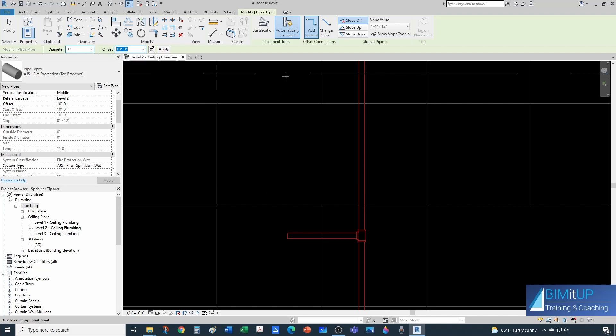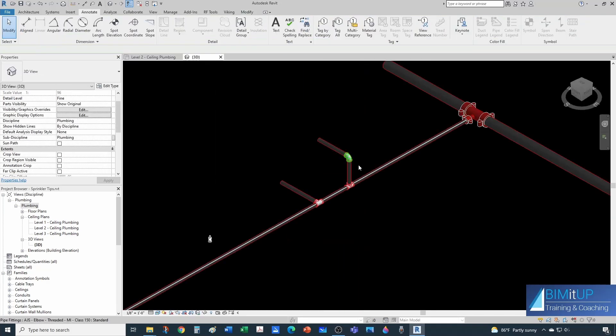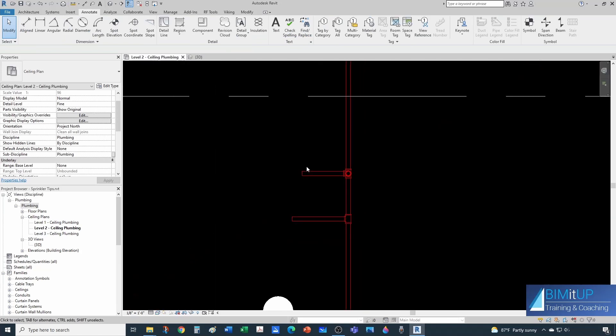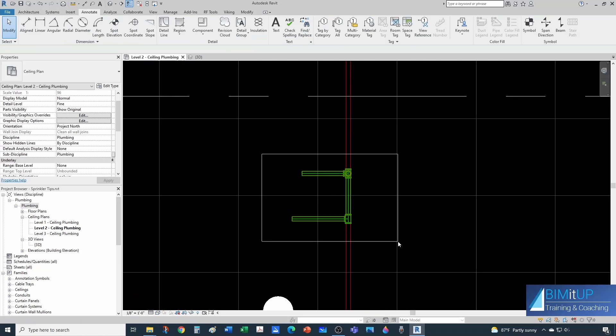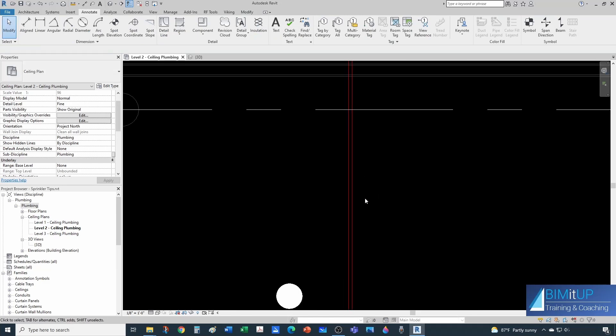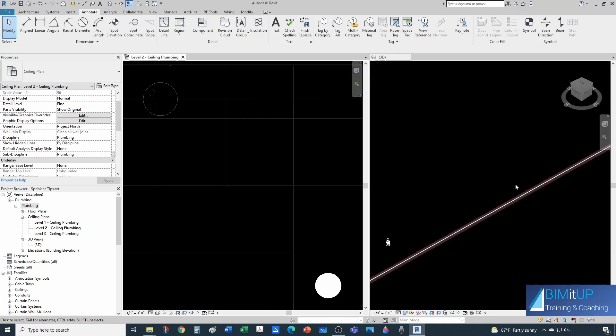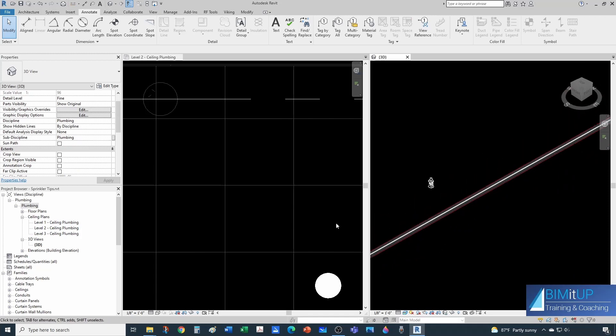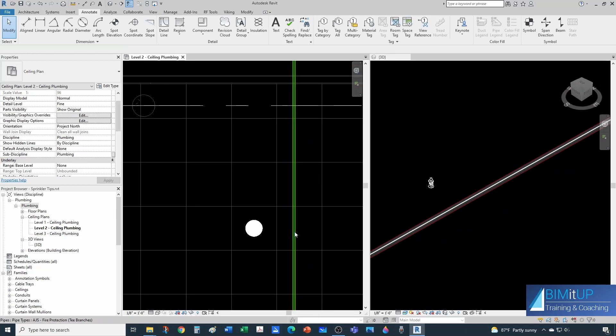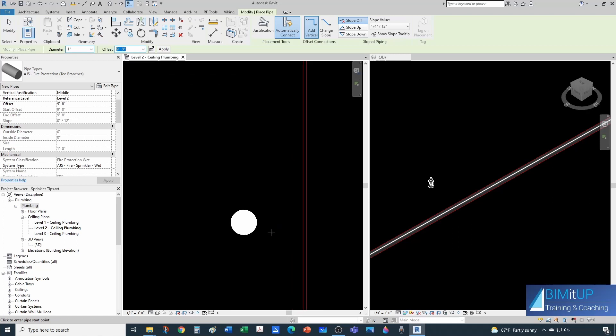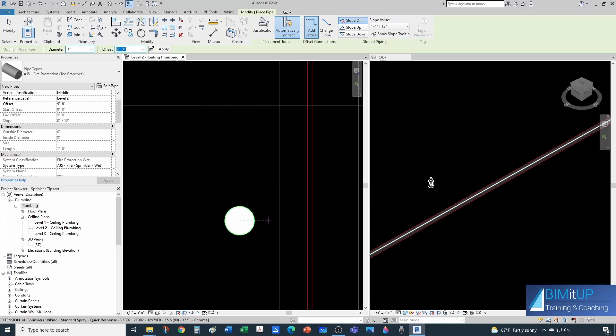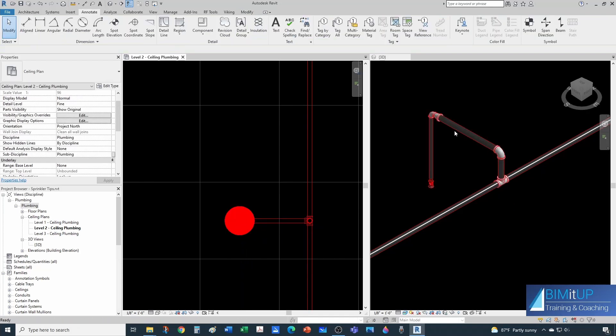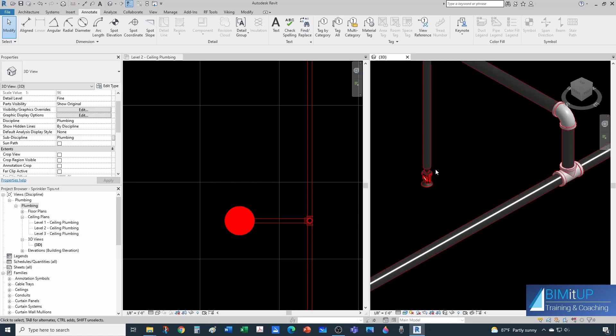If we go to our 3D view, this is what happened. I'm gonna heal this gap. Instead of being frustrated about it, we can take advantage of it. I'm gonna split my windows here so you see how nice this is for creating arm-overs. If I do my piping at let's say 9 feet 8 inches, and I am tracking the location of the sprinkler, and I click here and I click here, it automatically created an arm-over for me.